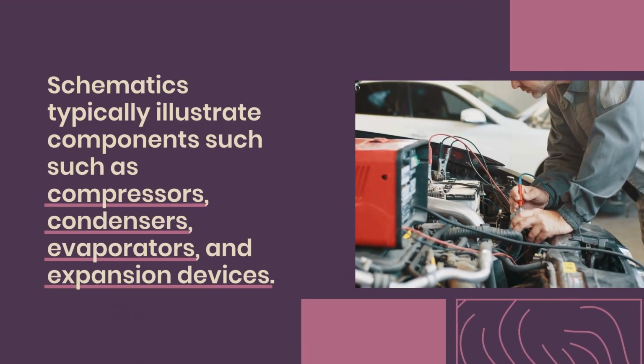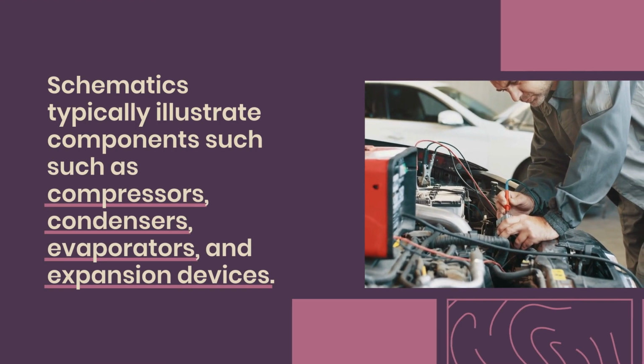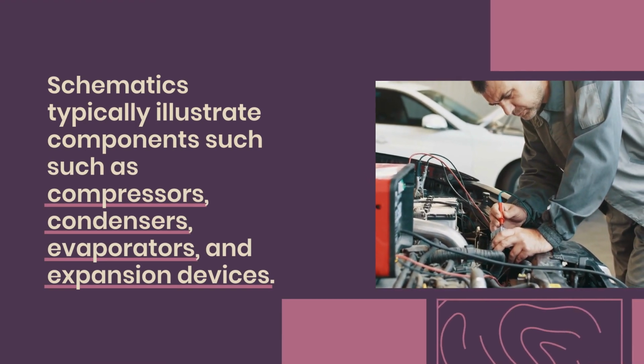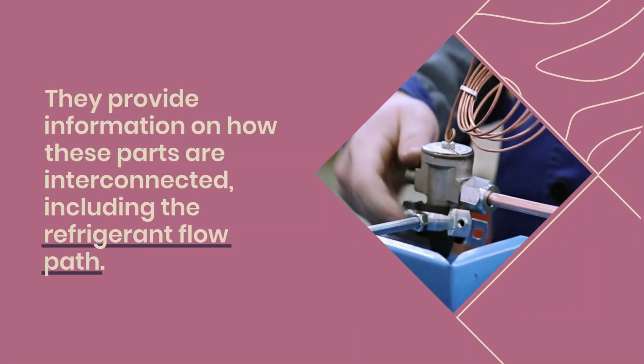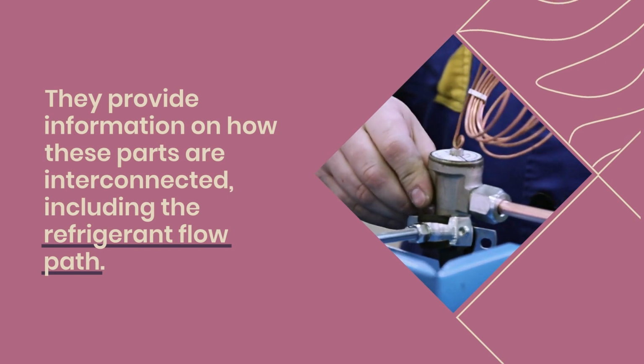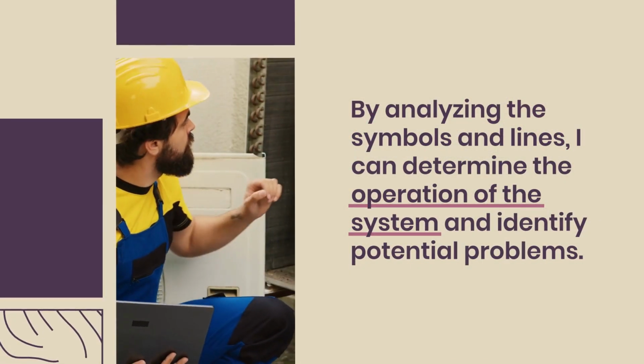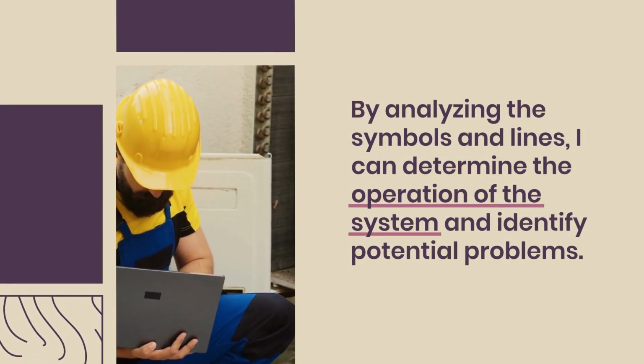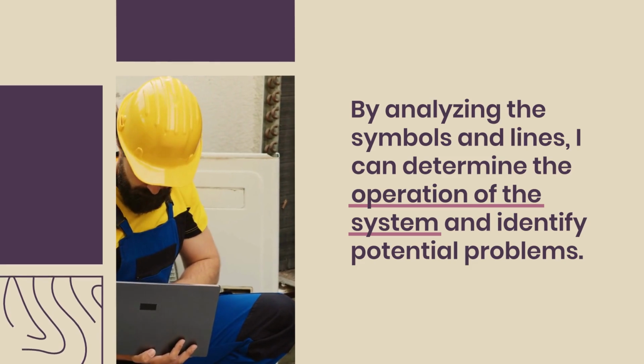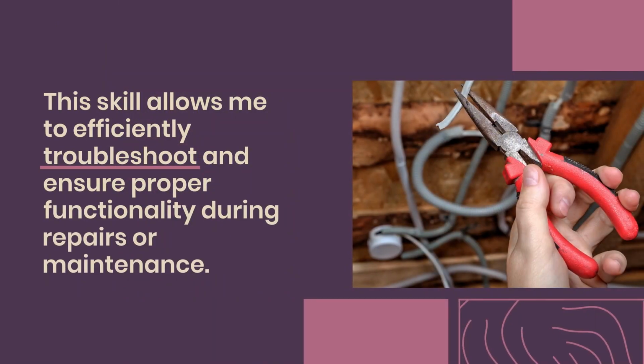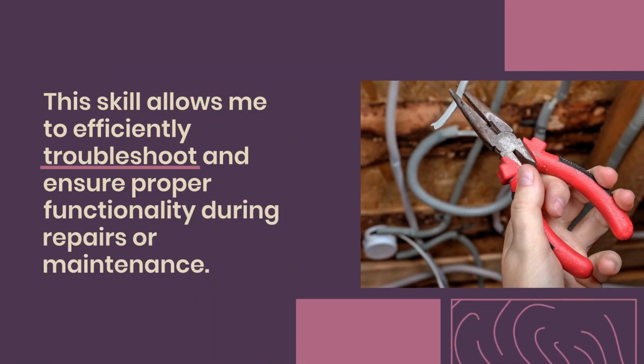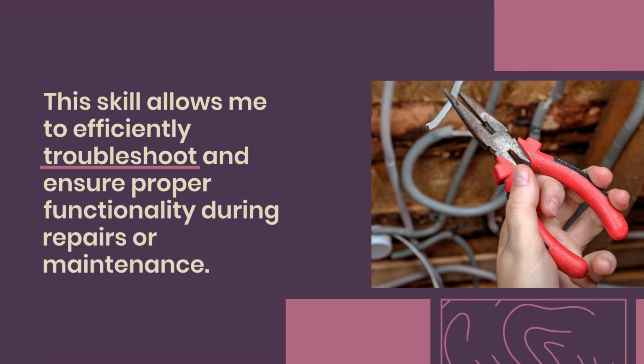Schematics typically illustrate components such as compressors, condensers, evaporators, and expansion devices. They provide information on how these parts are interconnected, including the refrigerant flow path. By analyzing the symbols and lines, I can determine the operation of the system and identify potential problems. This skill allows me to efficiently troubleshoot and ensure proper functionality during repairs or maintenance.